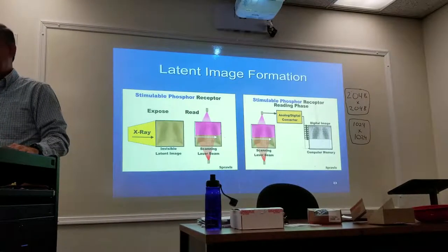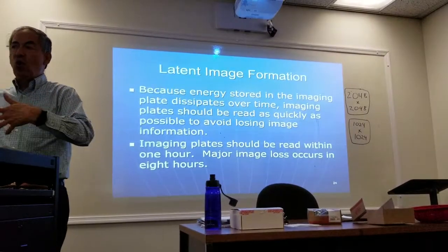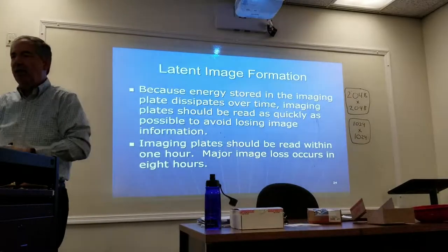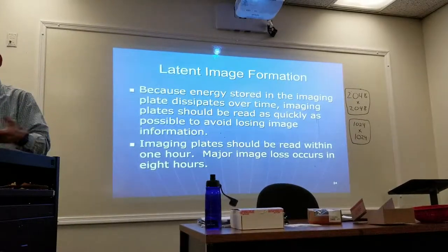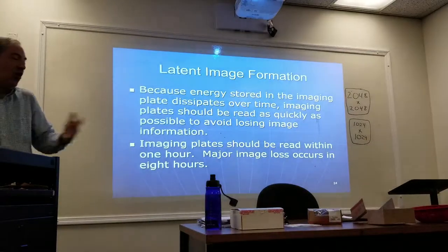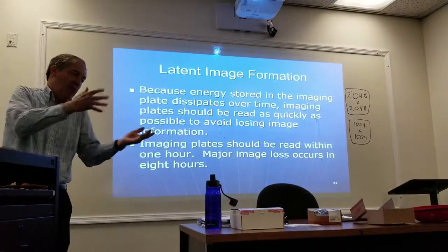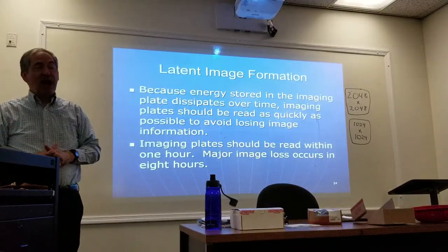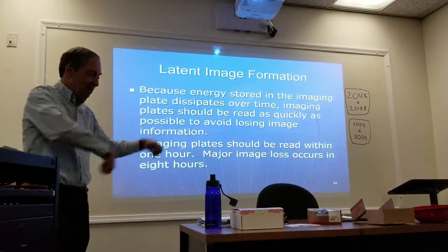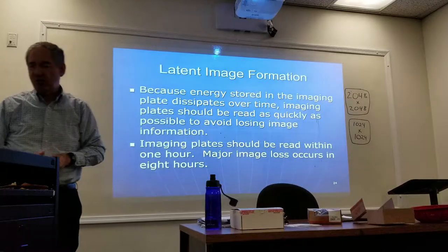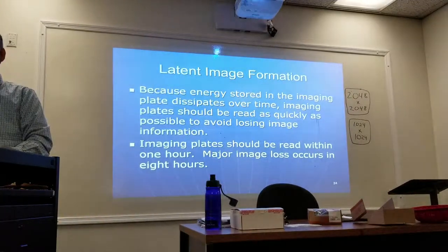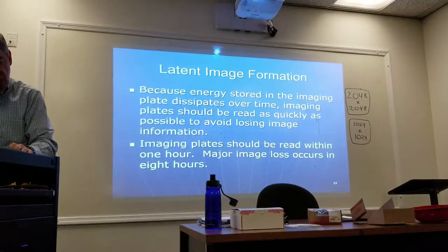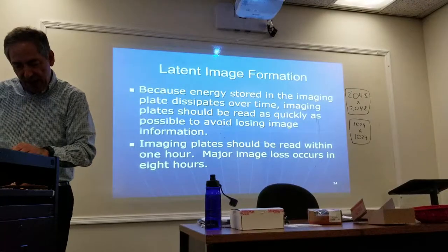Because energy stored in the imaging plate dissipates over time, imaging plates need to be read quickly — there's a major loss after eight hours. With film, you could make an exposure and put it back in the bin, expose it weeks later — that's sometimes how double exposures happened. But with imaging plates, you're developing quickly, so it doesn't really have a big effect.